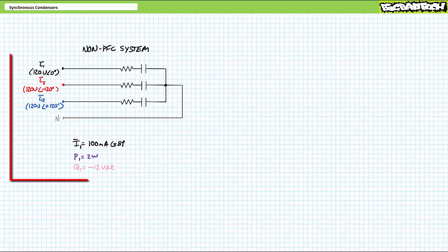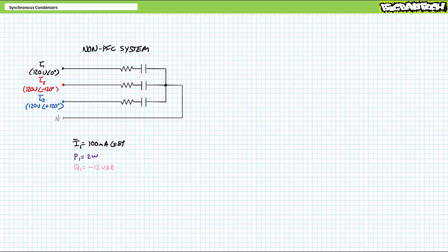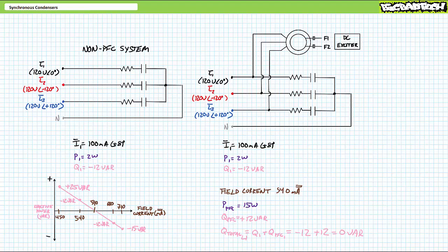Very rarely do you need to power factor correct a capacitive load since most industrial loads are inductive motors, but it does happen. Consider a scenario consisting of a balanced Y configuration of slightly capacitive impedances. In the non-power factor corrected scenario, each phase draws 100 mA of current leading each phase by a relative 81 degrees. Each load appears to be consuming 2 watts of real power and negative 12 VARs of reactive power — well inside the correction range of this device. We would expect to slightly under-excite the rotor to consume an equivalent amount of positive reactive power. When we bring the synchronous condenser in parallel, each load continues to supply the same negative 12 VARs of reactive power per phase.